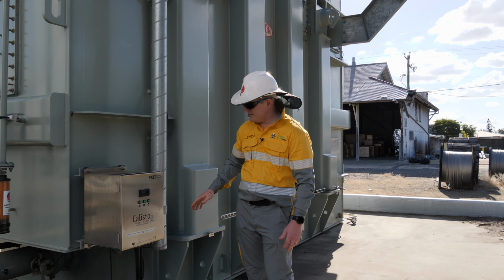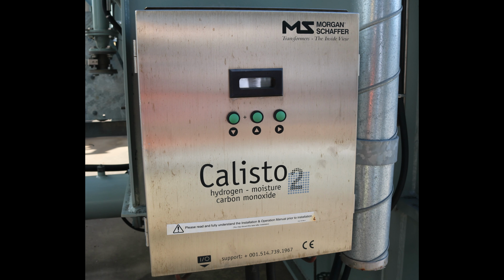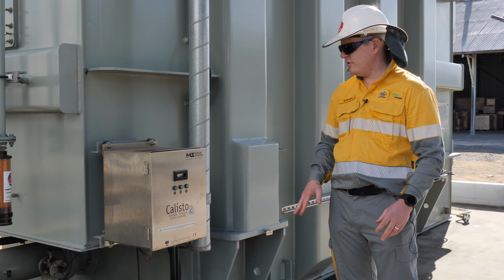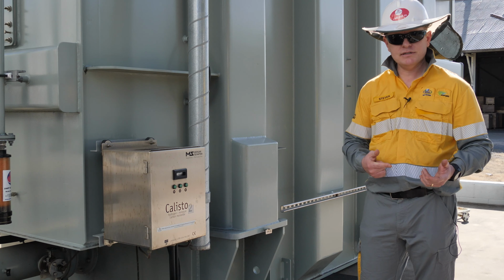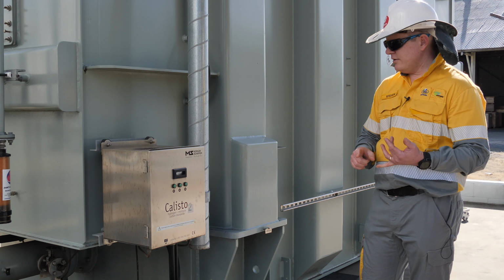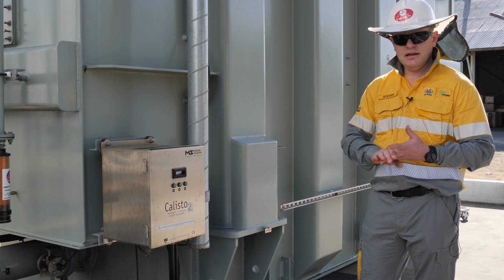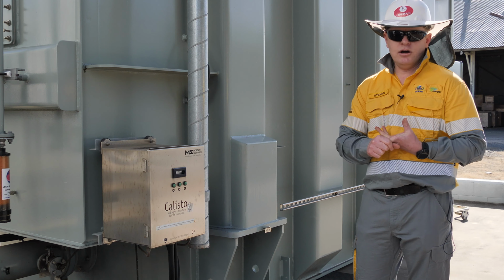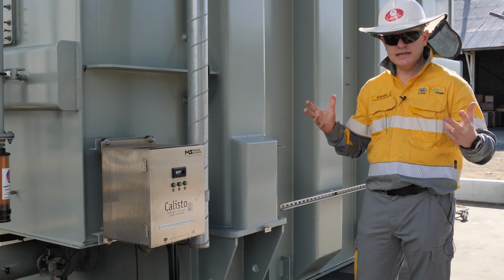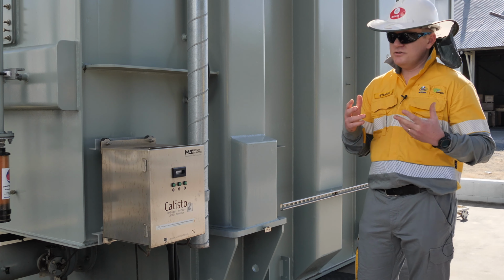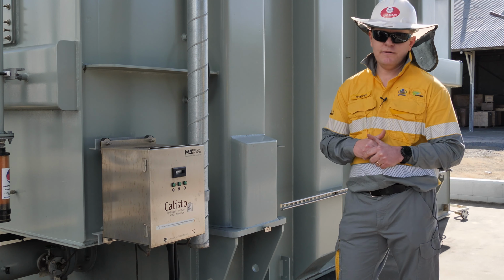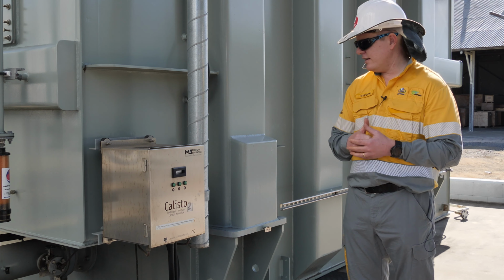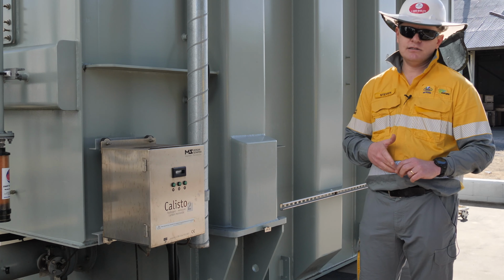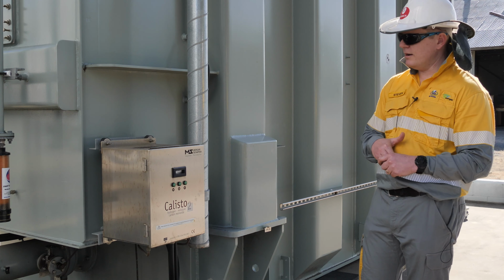Another important piece of equipment on this one is an online oil monitor. So transformer oil is a bit like blood. We can monitor different aspects of it to determine how well the transformer is performing. This unit here is called a Calisto, and it provides real-time monitoring of certain parameters in the transformer oil. This particular one monitors hydrogen, it monitors moisture, and it monitors carbon monoxide. Increases in hydrogen can mean that there is some kind of arcing or faulting energy inside the transformer that's producing gas. Moisture is really important. If you have too much moisture in your transformer oil, then the breakdown level of the oil can drop and you can have a flashover. And carbon monoxide is also an indicator for any sort of arcing or gas production within the transformer.